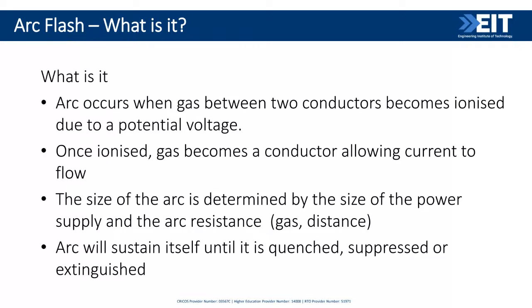Specifically, what does an arc flash involve? The arc is what occurs when a gas between two conductors — which is typically air, or in a switchgear mechanism it might be a different type of insulating gas — when that gas breaks down, it becomes ionised due to the potential voltage between your phases. When the gas becomes ionised, it can now become a conductor and you have current flowing from phase to phase — that's your arc. The size of that arc between your two conductors is determined by how much power you've got available to sustain that arc and what the resistance is between those conductors — essentially what is that gas composition and how far apart are the conductors.